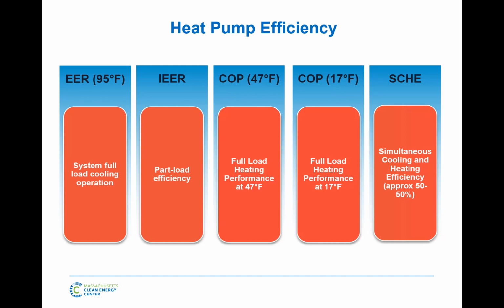This is what I was talking about earlier. These are the official ratings by AHRI, standard 1230 from 2010 for commercial VRF units. So EER, full load, IEER, part load. We do have 2 COPs, one at 47, one at 17F, which most people use. We don't have COPs below that. The manufacturers do, but it's not an official rating. Again, these are full load COPs, unfortunately.